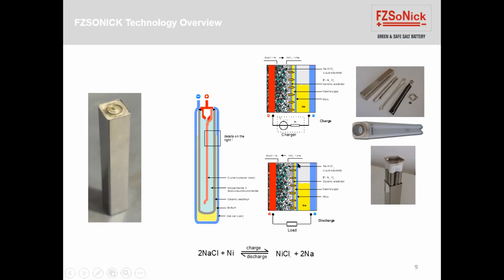This can happen because we install metallic springs that have two purposes: one is to give mechanical stability inside the cell, and the second is to create a capillary gap. This way, the sodium rises in the capillary gap and wets all the ceramic, making the full surface of the cell available for discharge mode.